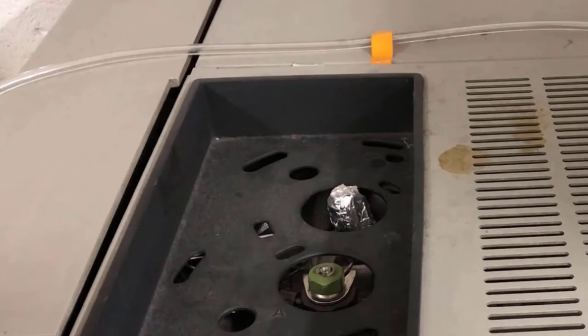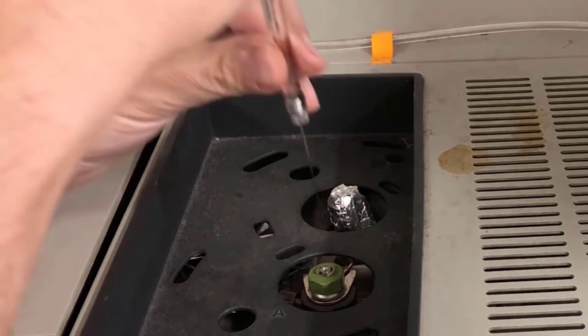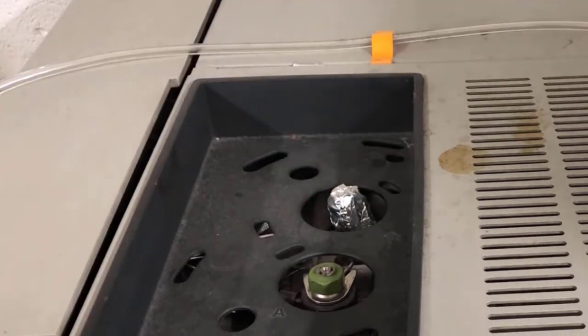Here's a close-up of the injector port. There's a hole that the needle goes through and underneath that is a rubber septum that the needle pokes through. Push the needle through the hole until the barrel bottoms out and then quickly press the plunger to inject the sample. If you hesitate on the plunger push, you can get a doubling of peaks in the chromatogram. Your chromatogram could look strange.